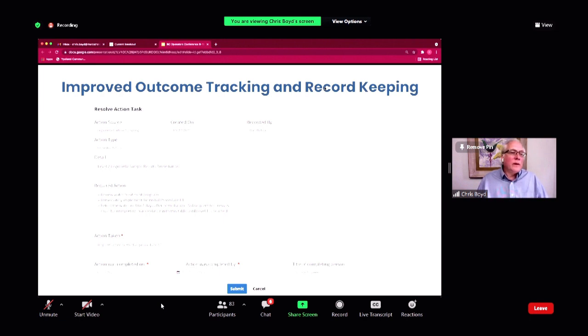And then when you get an outcome that triggers a corrective action, you start to say, okay, what do we do next? What are the required actions that get triggered from that result? In this example, review the water treatment program, immediately implement remedial procedure number 1, as defined in the water management plan. That's your internal policy, your internal duty of care that is defined. This is how we approach remedial action when we get a high Legionella result for a cooling tower. You define that.